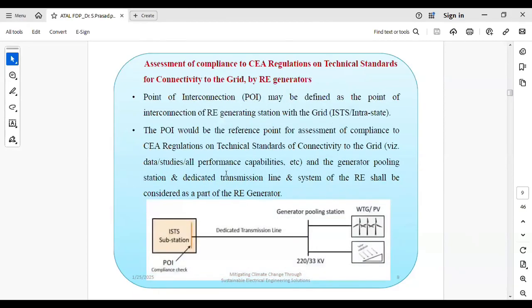When we are going for a grid connected solar PV system, first we have to take the reference as a point of interconnection. What is the point of interconnection? That means the point of interconnection of a renewable energy generating station with the grid. What is the bus at which you are going to inject the PV generators? That is the point of interconnection, which is considered to be the reference point where all the studies have to be assessed.